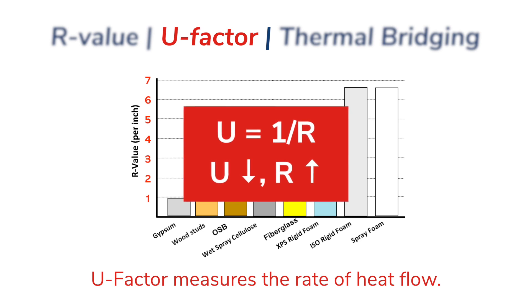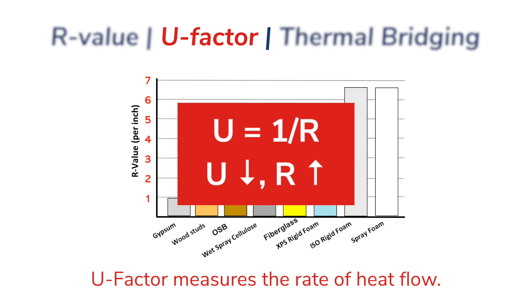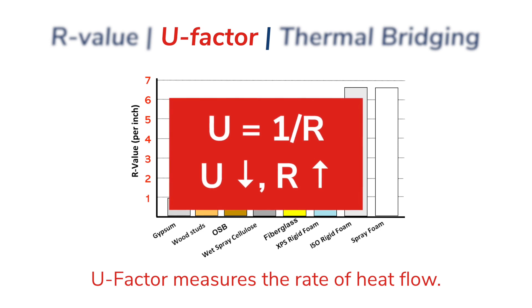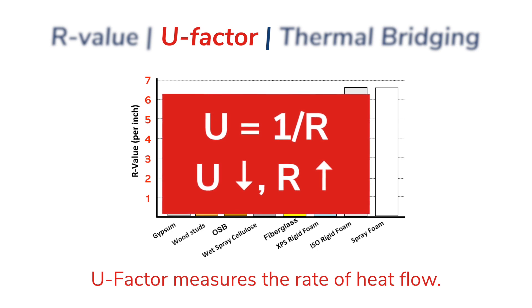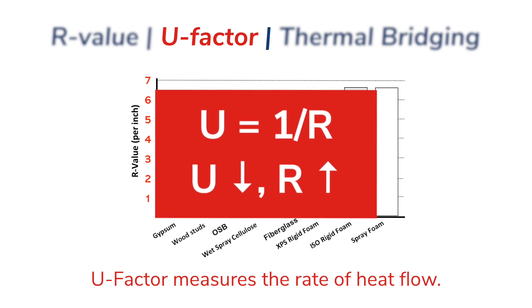U-factor, on the other hand, measures the rate of heat transfer and has historically been used as a metric to compare the thermal performance of window units. Assembly U-factors represent the overall thermal performance of a wall assembly better than looking at the R-values of individual components and adding them up. To summarize, the lower the U-factor of an assembly, the more energy efficient it is as a whole.